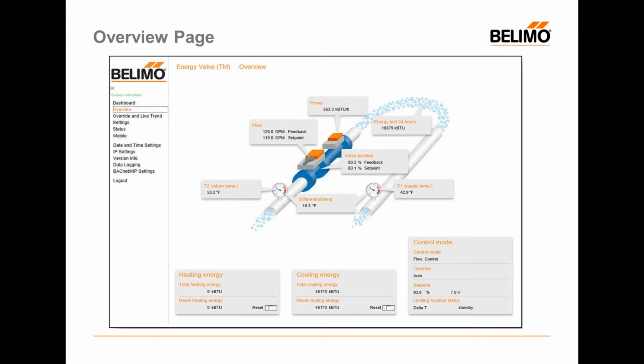The other thing it will let you know is the status of the delta T functioning limit, and that will let you know, are we in delta T limiting mode? Are we in standby mode? Has delta T manager not been enabled or not been selected for use? So that is our overview page.